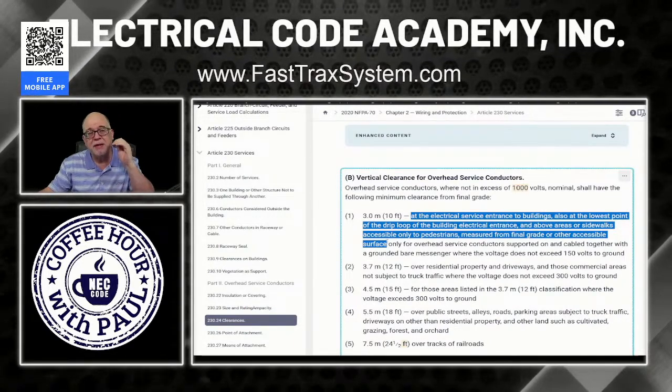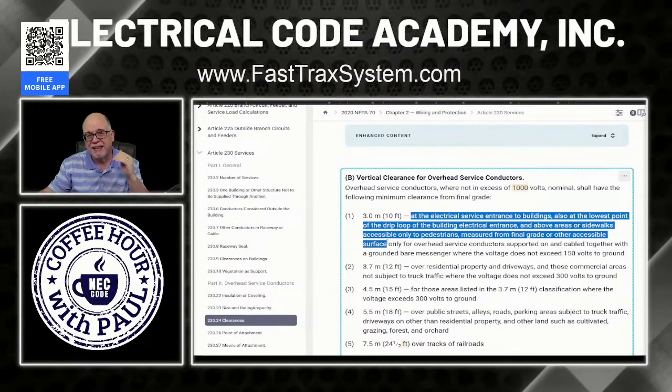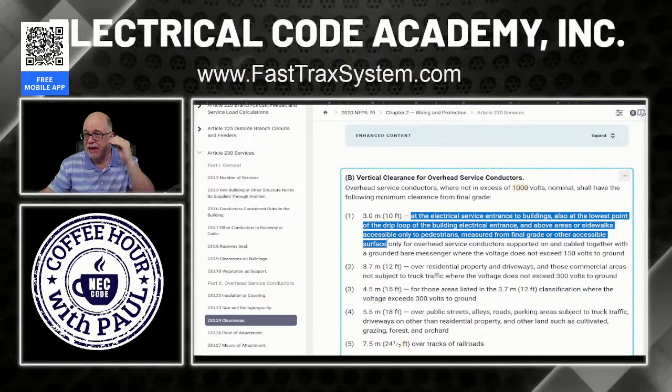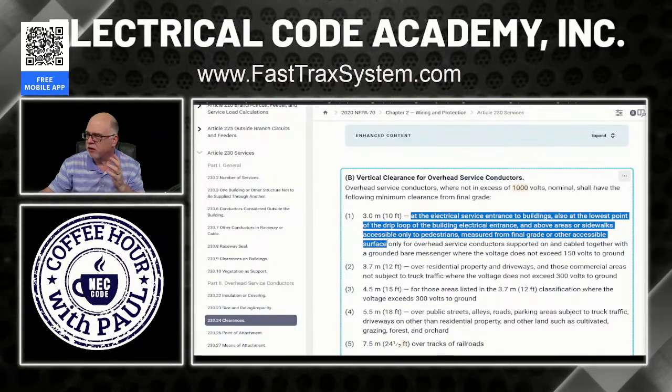The conductors might have to be at least 8 feet, but then if it's an accessible rooftop, then you gotta worry about that 10-foot clearance to the drip loop. That might cause those conductors to have to move up higher. See how the code works? So many things get intertwined here, all right?